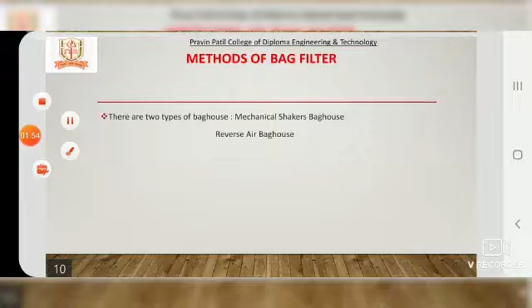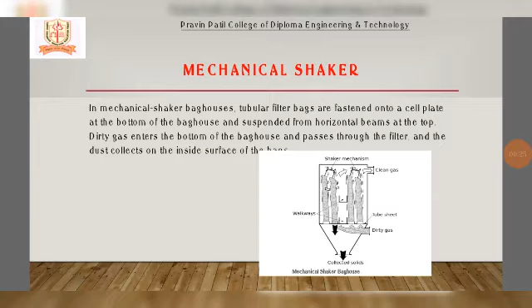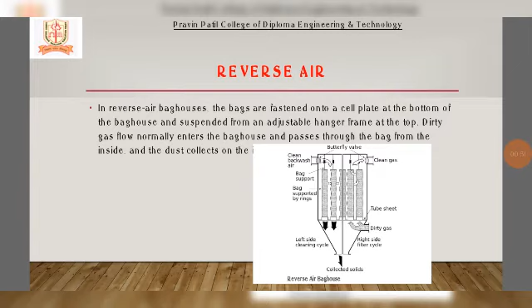Types of baghouse. There are two types of baghouse: mechanical shaker baghouse and reverse air baghouse. In a mechanical shaker baghouse, tubular filter bags are fastened onto a cell plate at the bottom of the baghouse and suspended from a horizontal beam at the top. Dirty gas enters the bottom of the baghouse and passes through the filter, and the dust collects on the inside surface. Reverse air: in a reverse air baghouse, the bags are fastened on a cell plate at the bottom of the baghouse and suspended from an adjustable hanger frame at the top. Dirty gas flow normally enters the baghouse and passes through the bag from the inside.